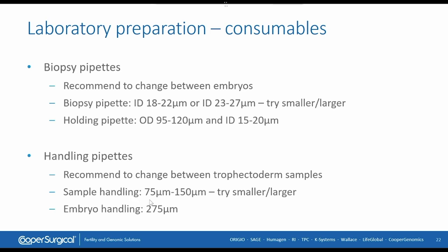For sample handling pipettes, we recommend between 75 and 150 micrometers, though some operators prefer larger pipettes. Smaller than 75 micrometers is more difficult. For embryo washing, we advise a 275 micrometer pipette, because if you go smaller, you risk removing the blastocyst from its zona pellucida.